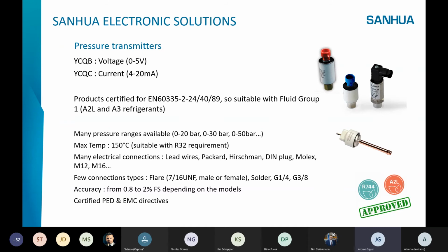We have many electrical connections, for example, lead wires. We also have Packard connector, the blue or the red. We have Hirschmann in black. We have DIN plug. I don't put the photo, but we have DIN plug, Molex, M12, M16. So this is for electrical connection. And for refrigerant connection, we have a flare, very common. We also have solder, which is recommended for A2L or for flammable, for propane. We also have G1/4 or G3/8.